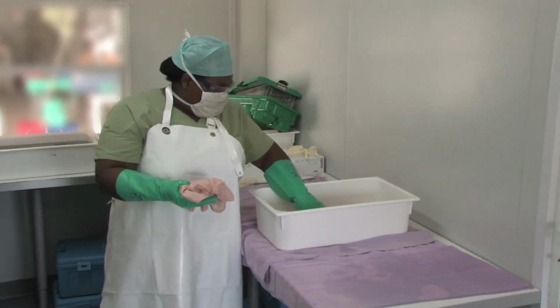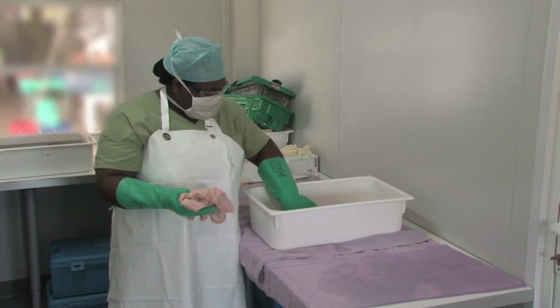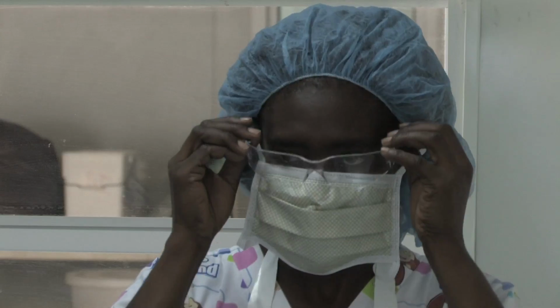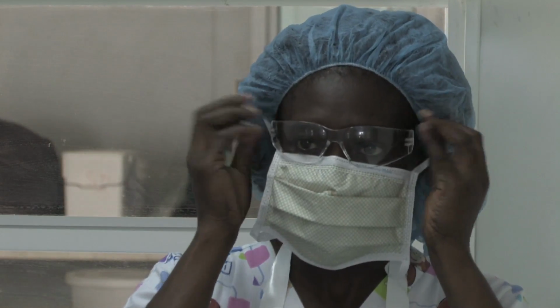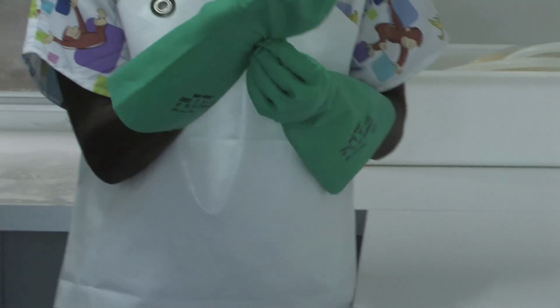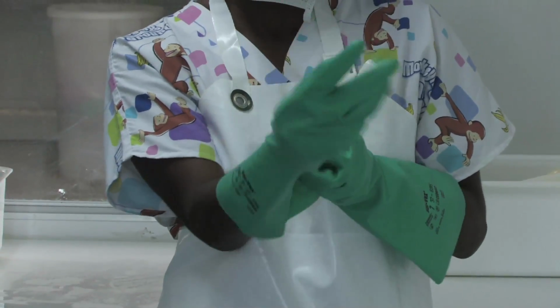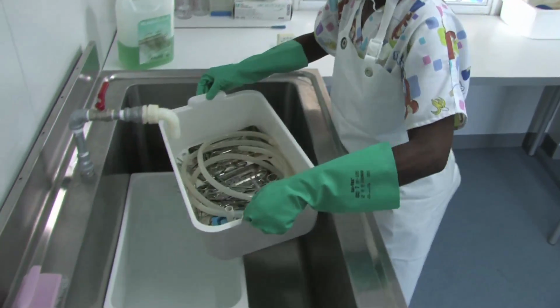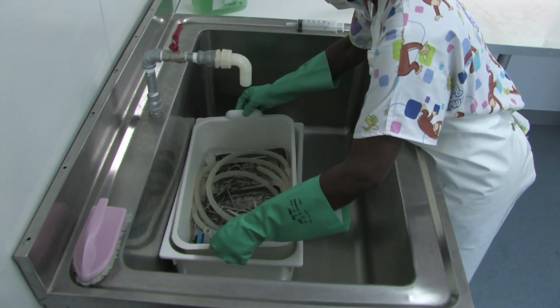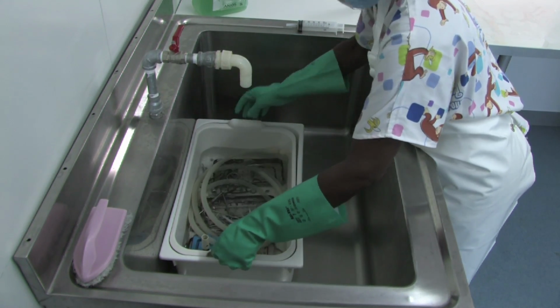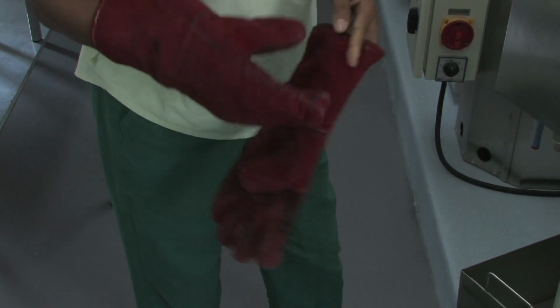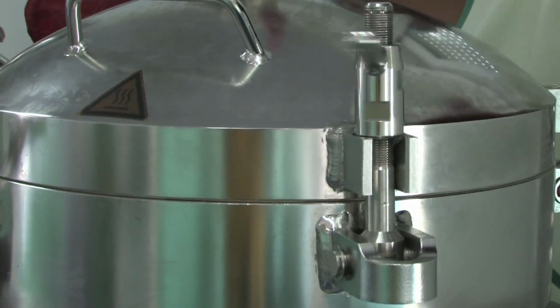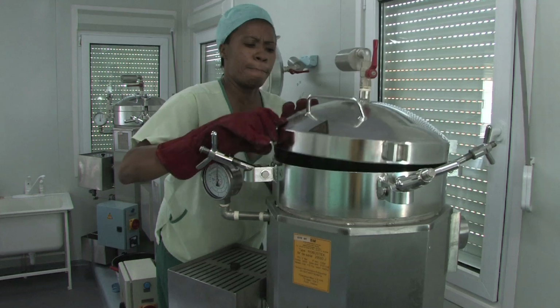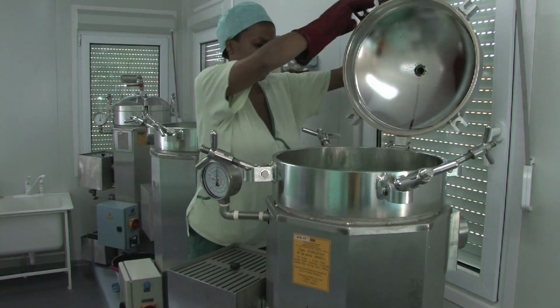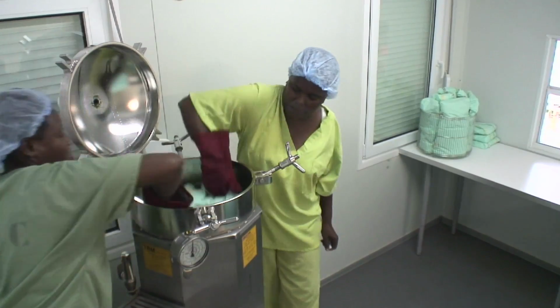The staff in charge of washing instruments should protect themselves from accidental exposure to blood with safety glasses and thick gloves. A plastic apron should be worn during washing to protect work clothes. The staff in charge of sterilization should use heat-resistant gloves for opening the autoclave and removing the metal baskets after sterilization.